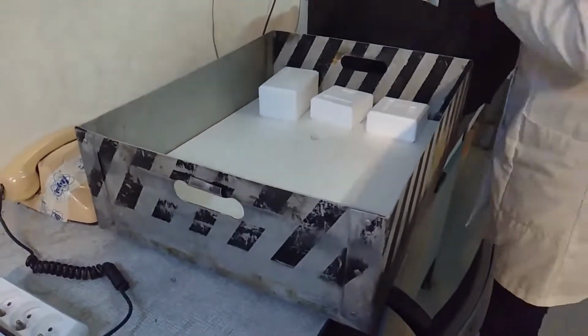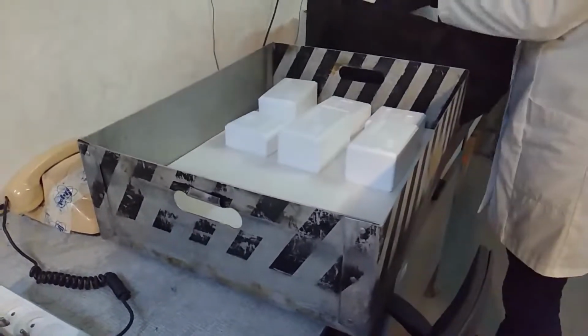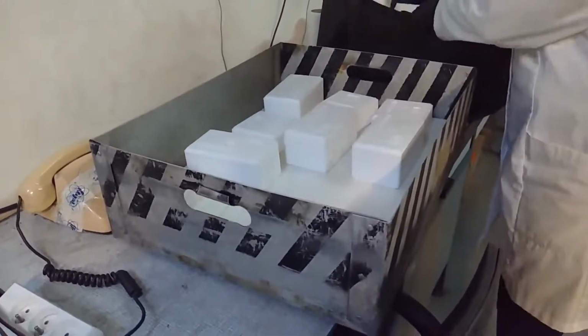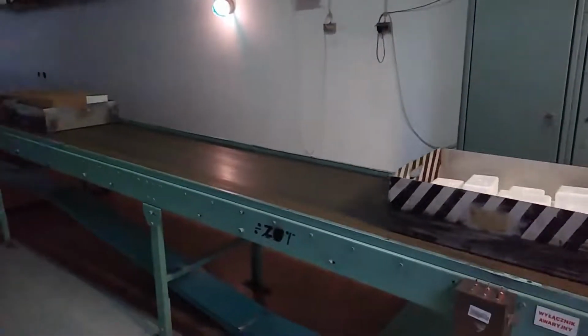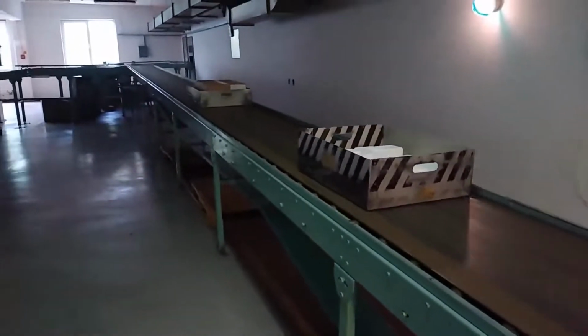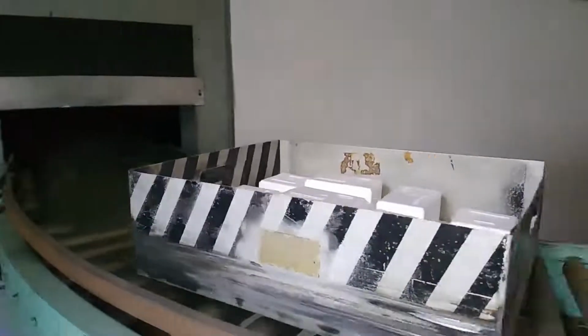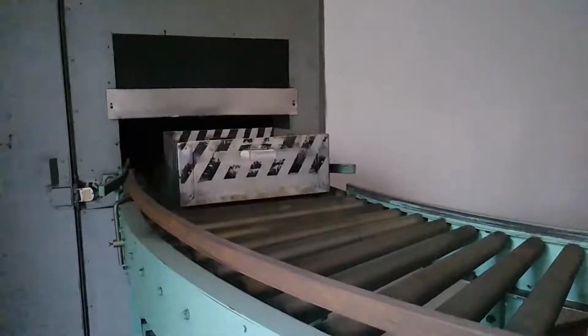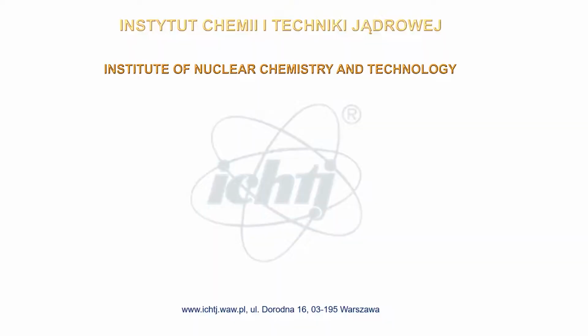In effect, a sterilization dose of 35 kilograys is achieved in a mass corresponding to the cell-free skin matrix at an exposure dose of only 25 kilograys. This careful design allows an increase in the sterilization process rate by almost one third, which in a similar relation reduces the cost of the sterilization process.